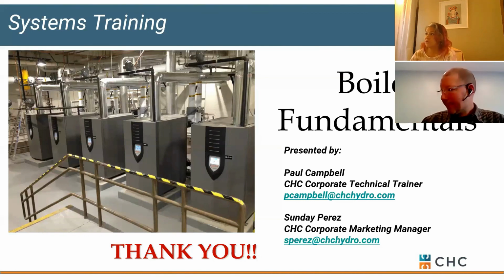Can you talk a little bit about minimum flows for different types of boilers as well as minimum system volumes? Oh boy, that's a loaded question, a really good question. I don't know that I can talk too much about it other than it's something that we need to consider when we're laying out a system and selecting a boiler. So every boiler has minimum flow requirements to it. Some manufacturers will tell you they have no minimum flow requirements.